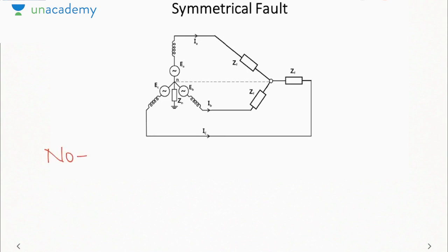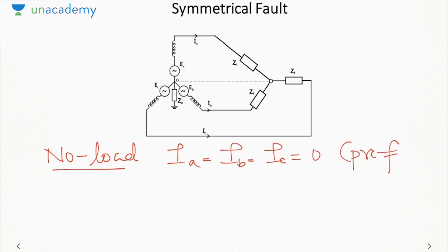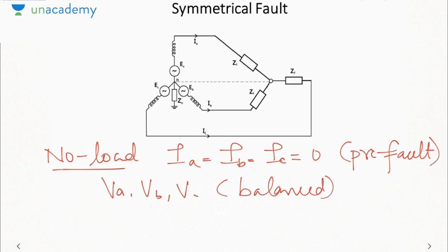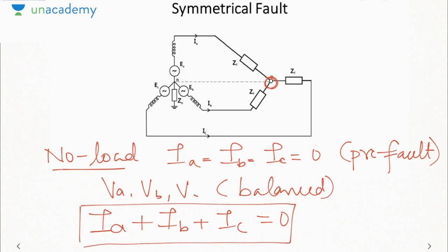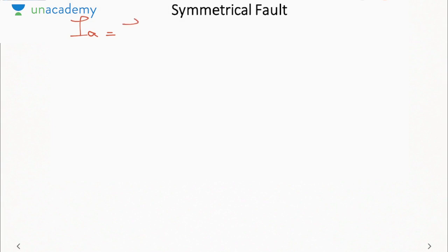First of all, the first assumption that we will make is a no load condition prior to the fault. No load condition means IA, IB and IC were all 0 before the fault, that is, pre-fault. And VA, VB, VC were all balanced. Now when the fault occurs, if we apply KCL at this node, we see that there are three incoming currents, IA, IB and IC. There is no outgoing current, so the sum must always be 0. So they will always be balanced, that is, IA will be IA angle 0, IB will be IB angle minus 120, IC will be IC angle 120.